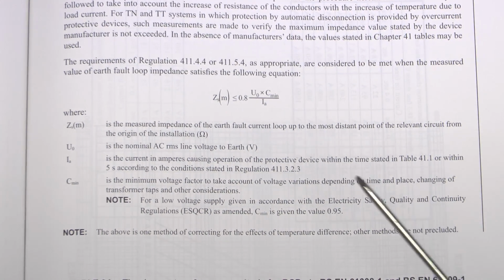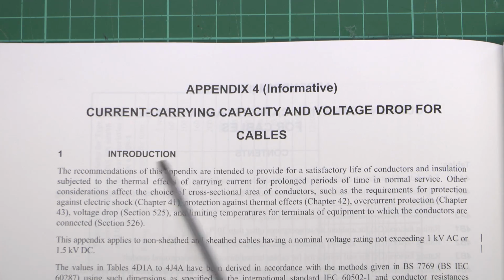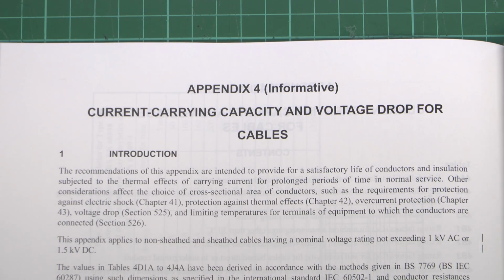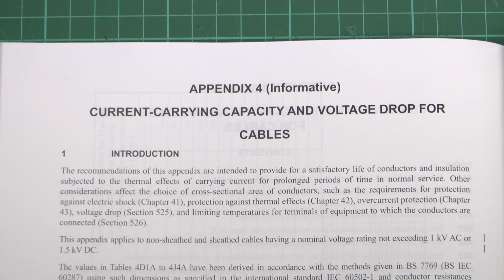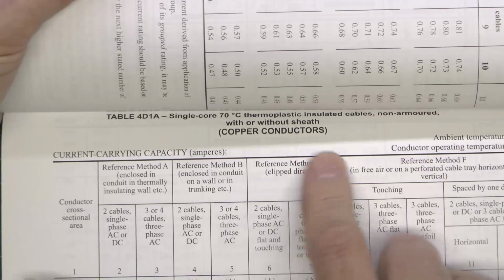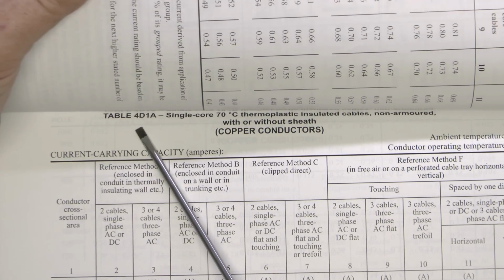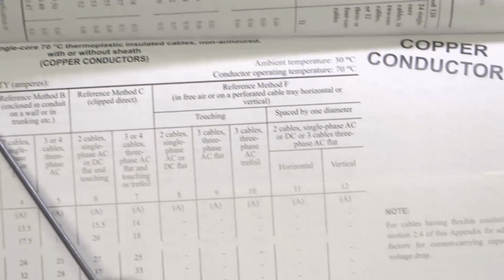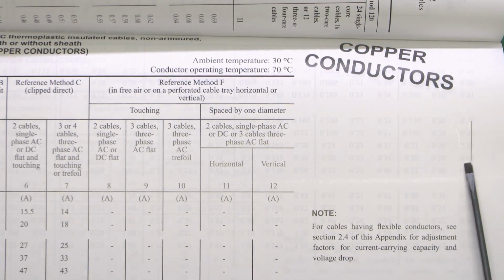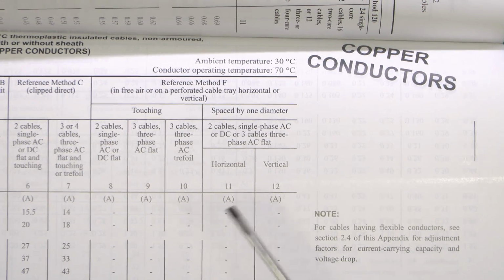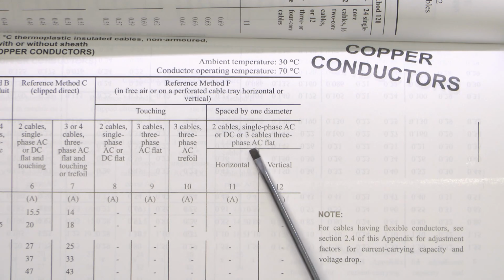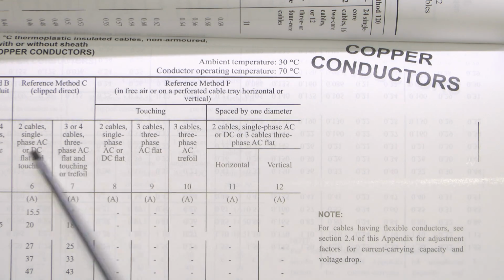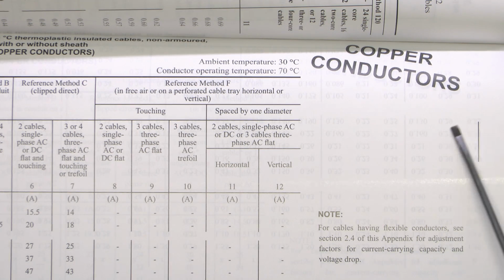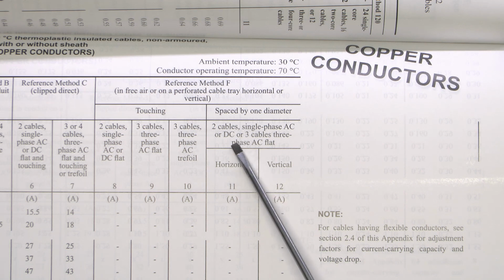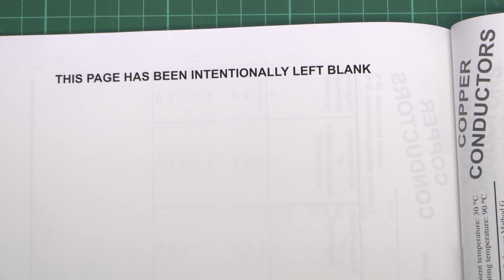Now Appendix 4, quite a lengthy one, covers current carrying capacity and voltage drop for cables. There's a number of changes marked, but they're all pretty much irrelevant and of no consequence. All of the tables from 4D1A onwards have the mark in the margin suggesting changes, but all that's changed is AC and DC now in capital letters, previously lowercase, across all the columns. So although all the tables are marked as altering, in reality nothing is actually altered. And on page 410 we have the world's most useless page.